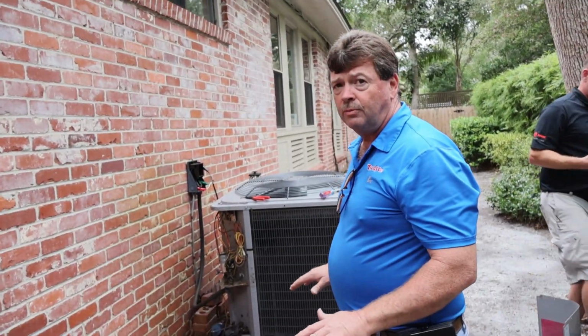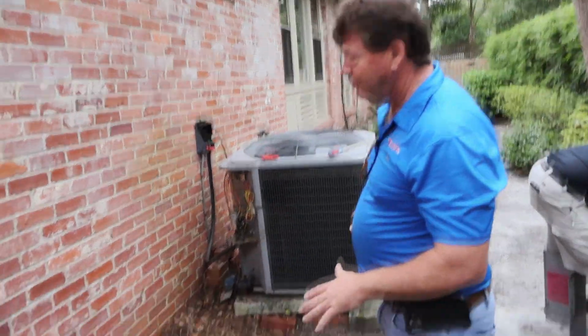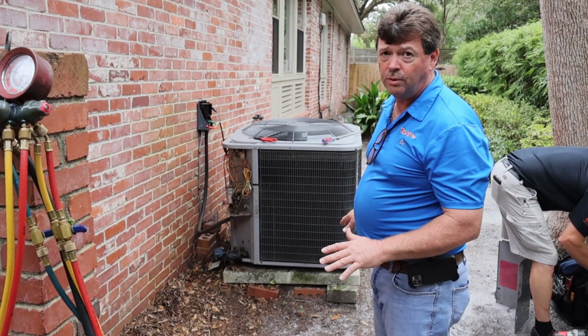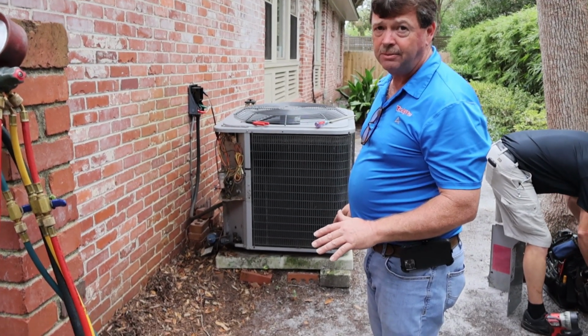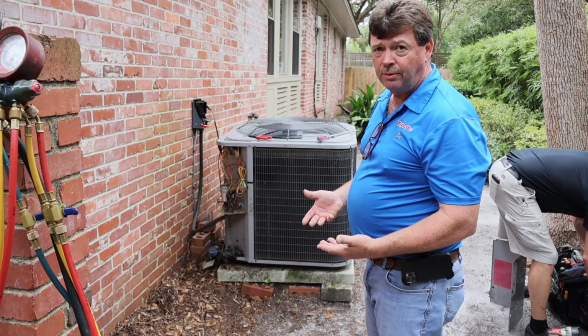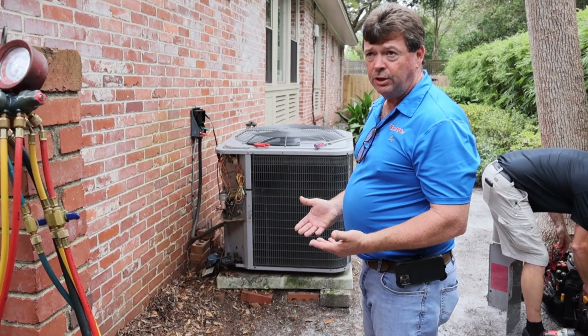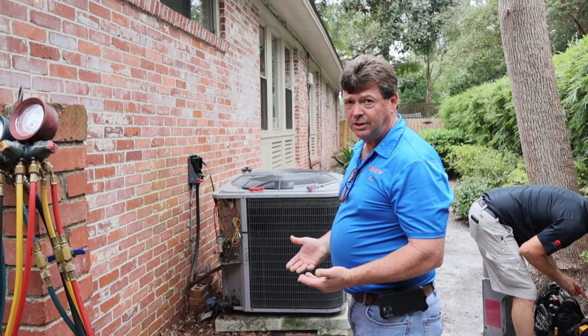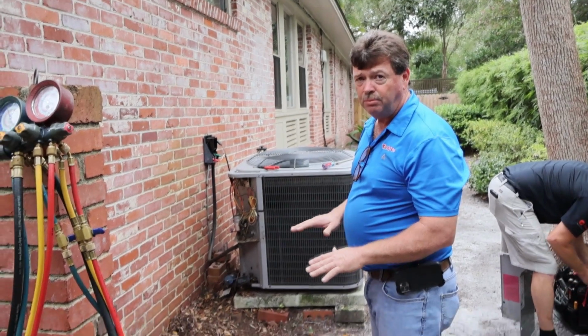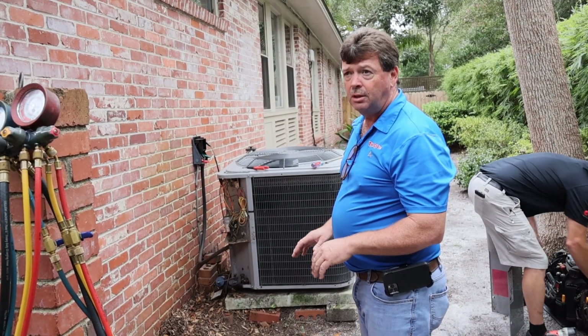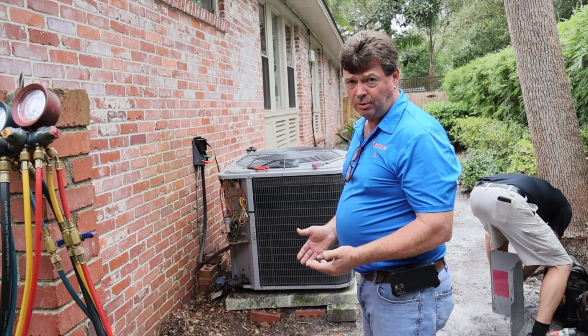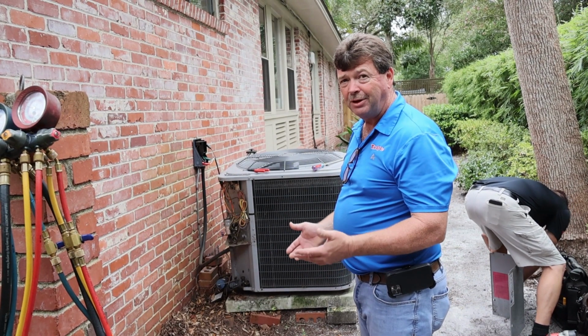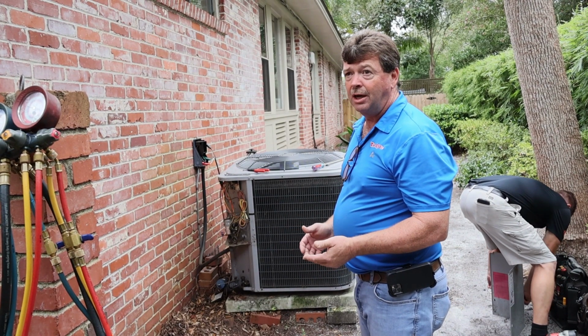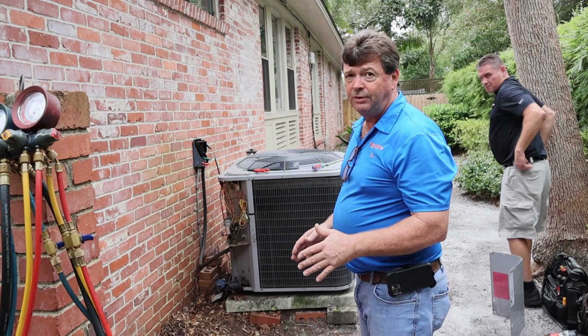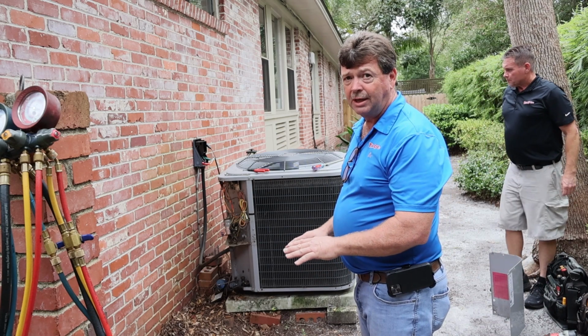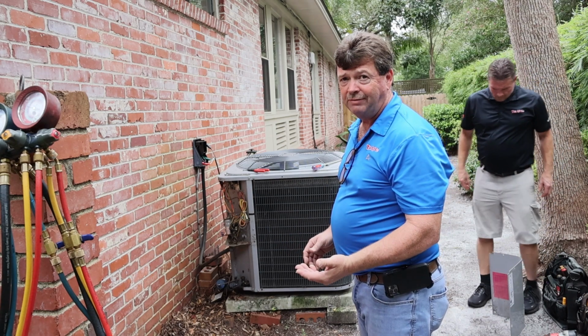For one, cosmetically it doesn't look good. For another, the oil that is located in the compressor is a reservoir, and if you are not level with your condensing unit, the lubrication of your moving parts in your compressor doesn't get lubricated properly. So from that standpoint, it really does need to be level, because lubricating moving parts in a motor like that is very important for longevity.